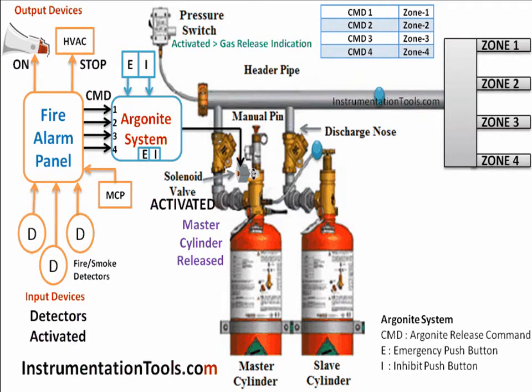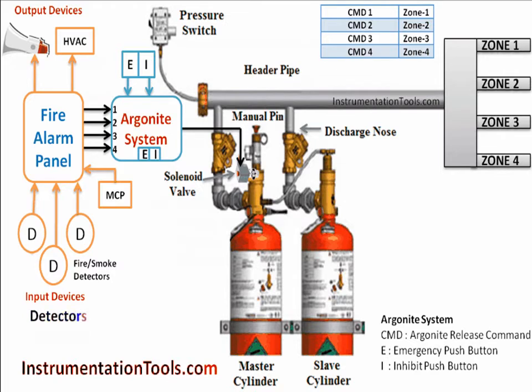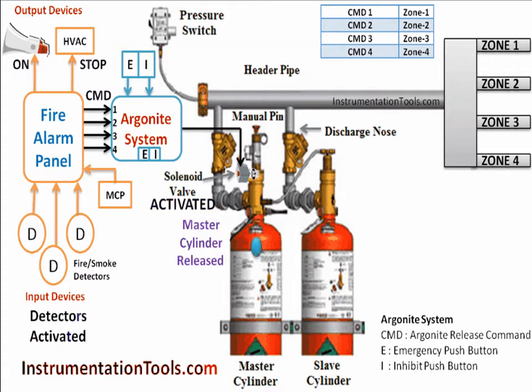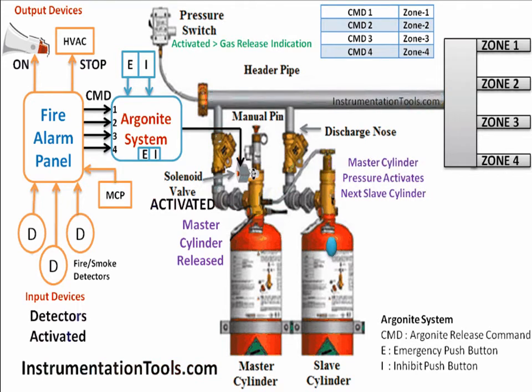If inhibit is not given and the time delay expires, the Argonite System activates the solenoid valve on the master cylinder. The master cylinder gas is released and has two paths: one to the main discharge line and one to the next slave cylinder. The master cylinder pressure activates the slave cylinder, which is then also released. Similarly, the slave cylinder may also have two paths — one to the main discharge line and one to the next slave cylinder.